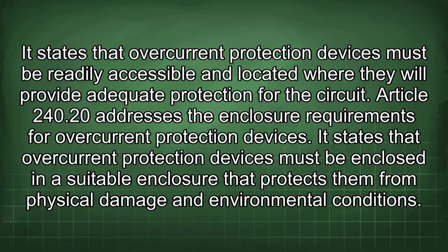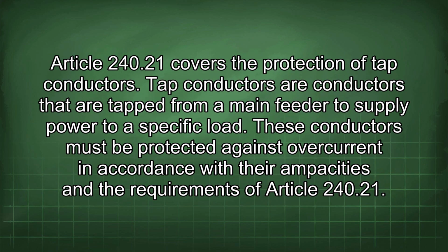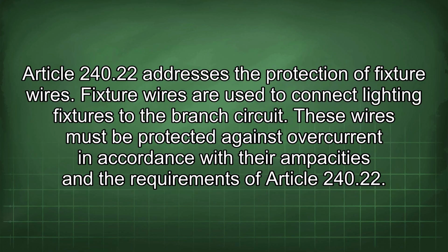Article 240.20 addresses the enclosure requirements for overcurrent protection devices. It states that overcurrent protection devices must be enclosed in a suitable enclosure that protects them from physical damage and environmental conditions. Article 240.21 covers the protection of tap conductors. Tap conductors are conductors that are tapped from a main feeder to supply power to a specific load. These conductors must be protected against overcurrent in accordance with their ampacities and the requirements of Article 240.21. Article 240.22 addresses the protection of fixture wires. Fixture wires are used to connect lighting fixtures to the branch circuit.